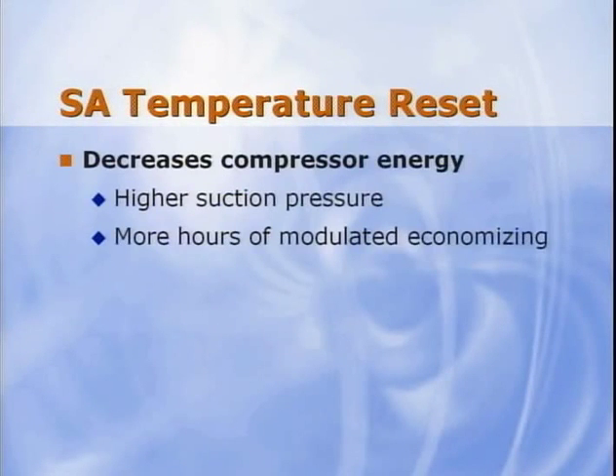First of all, increasing the supply air temperature reduces compressor energy because it allows the compressor to operate at a warmer suction temperature. This equates to a higher suction pressure, which reduces the compressor lift and correspondingly reduces compressor kW. In addition, supply air reset increases the benefit of an airside economizer. Using a reset strategy, when the outdoor air is cooler than the supply air set point, the compressors are shut off and the outdoor and return air dampers modulate to deliver the desired supply air temperature. A higher supply air temperature set point allows the compressors to be shut off sooner and increases the number of hours when the economizer provides free cooling.